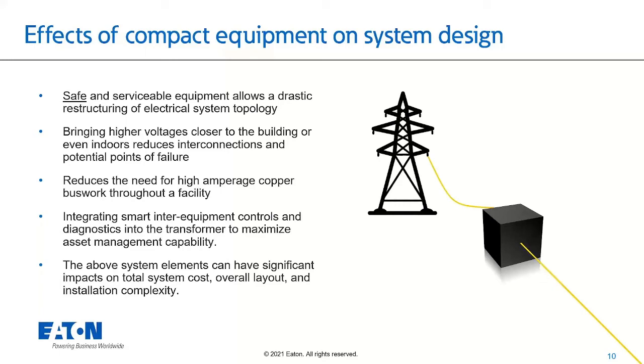The obvious benefit of eliminating unnecessary components is we get an overall smaller system. Hopefully that reduces cost, reduces overall layout complexity, and ultimately installation complexity. I mentioned interconnecting an MV switch with current transformers and relaying, doing that all on site. If we can consolidate that package into more of a single piece of equipment, that reduces the headache on site and makes the install time greatly reduced and much less complex.